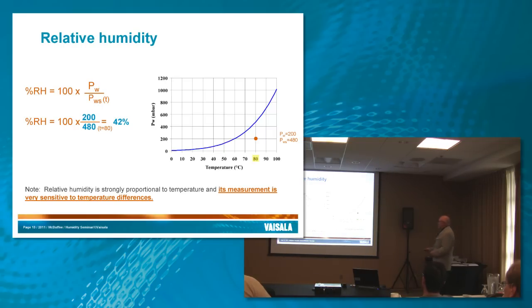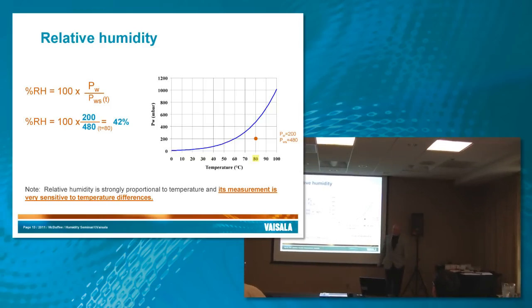So if you have a point here on the chart, this point here, you've got a PW measured at 200, and a PWS at 480. So we'd go up here and across. So your relative humidity is 42%.